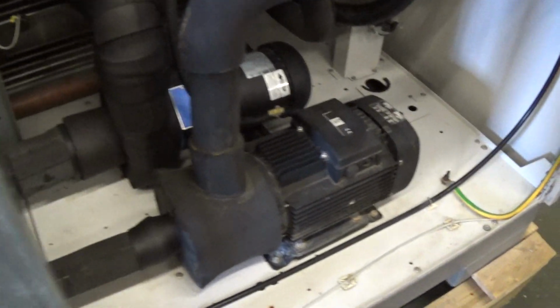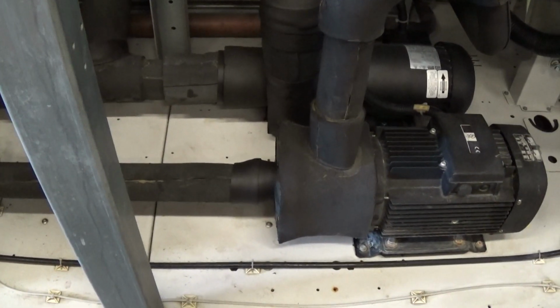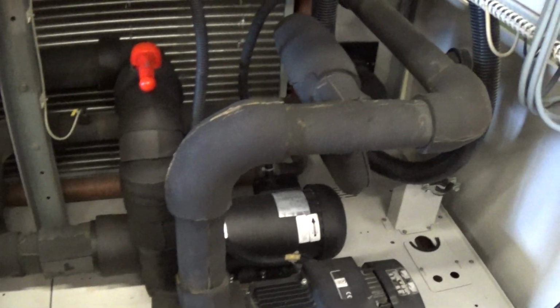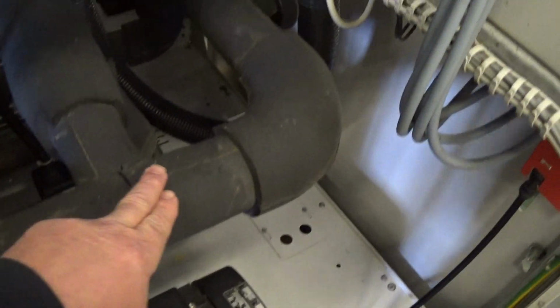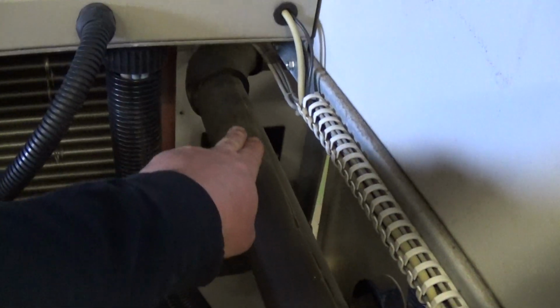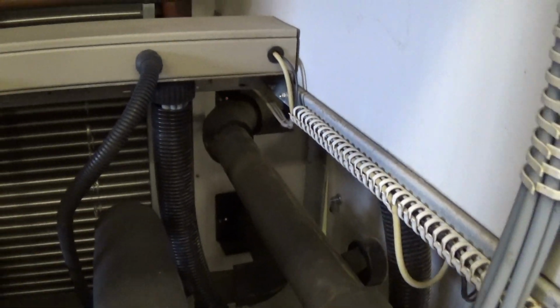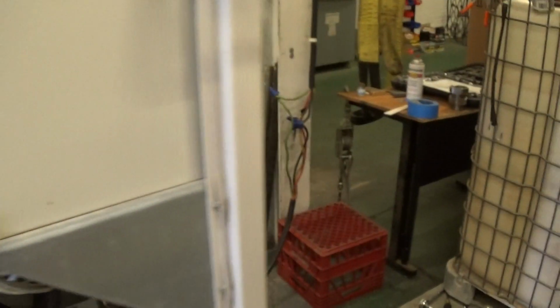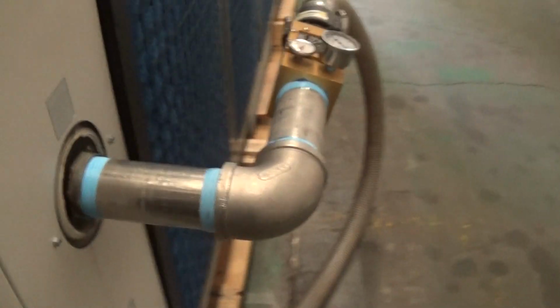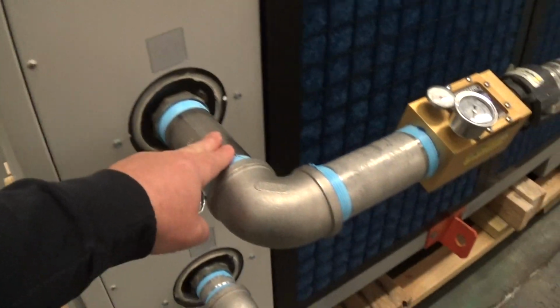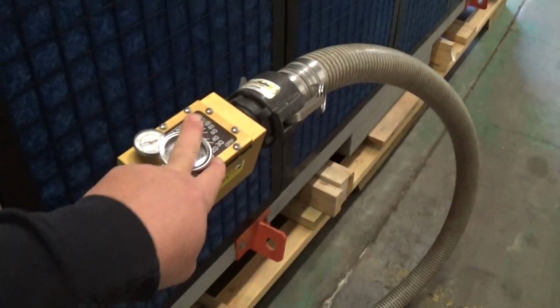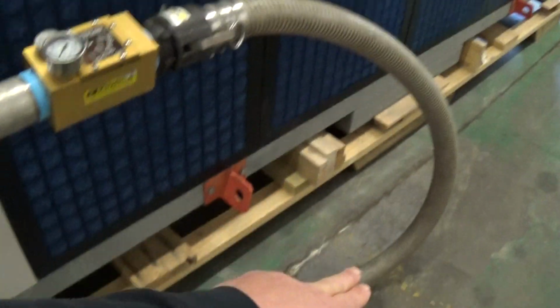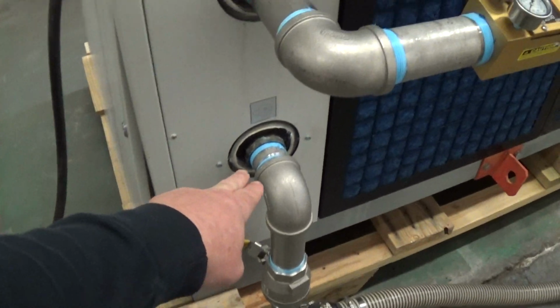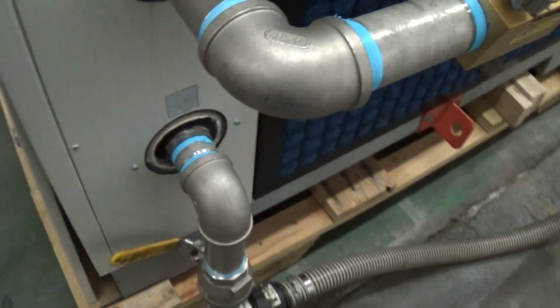Then the process pump is a slightly bigger pump here, this Grundfos pump. It draws from the chilled water in the tank and goes out to the process in the back of the chiller cabinet there. So we have 2-inch connections for our test loop. This is the output of the chiller, and we usually put on a flow gauge to test it, and we're just looping back to the input of the chiller.